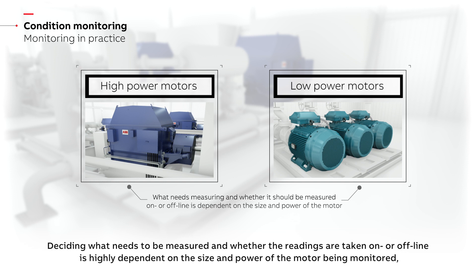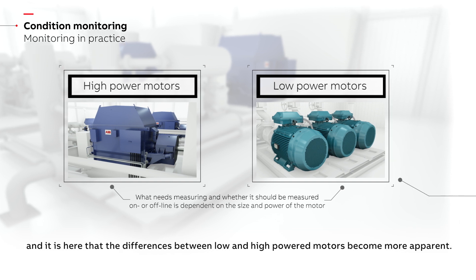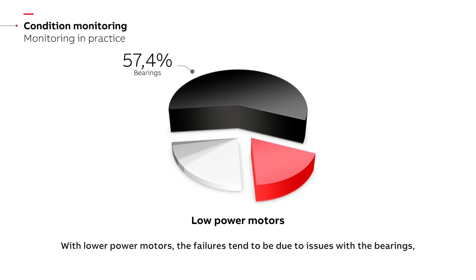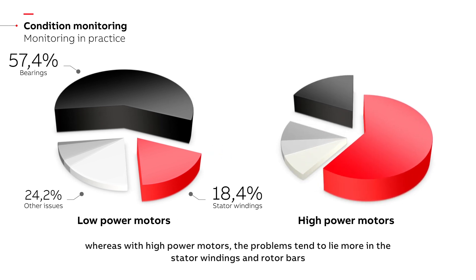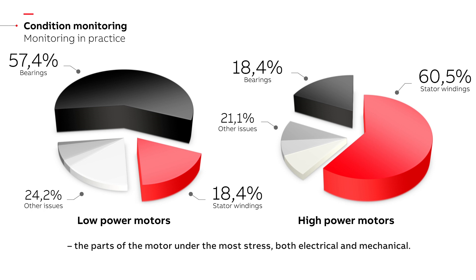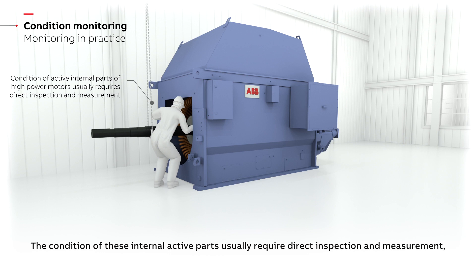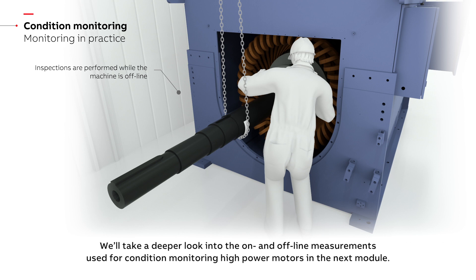It is here that the differences between low and high powered motors become more apparent. With lower power motors, the failures tend to be due to issues with the bearings, whereas with high power motors the problems tend to lie more in the stator windings and rotor bars — the parts of the motor under the most stress, both electrical and mechanical. The condition of these internal active parts usually requires direct inspection and measurement, so inspections are performed offline in addition to the online measurements taken while the machine is running.